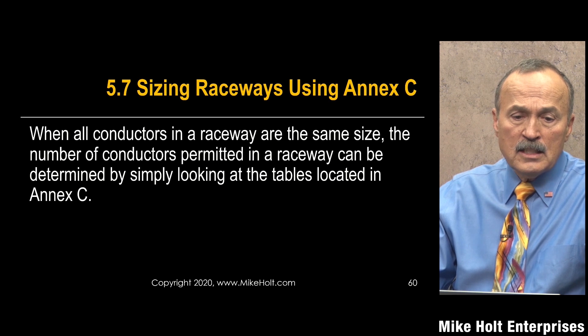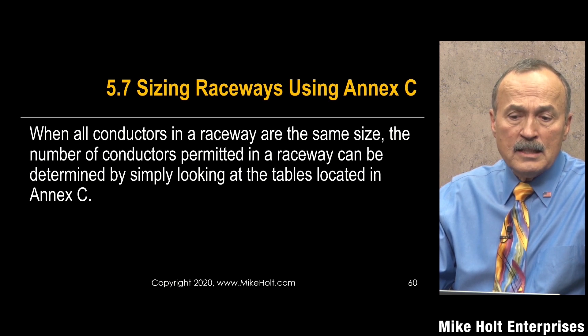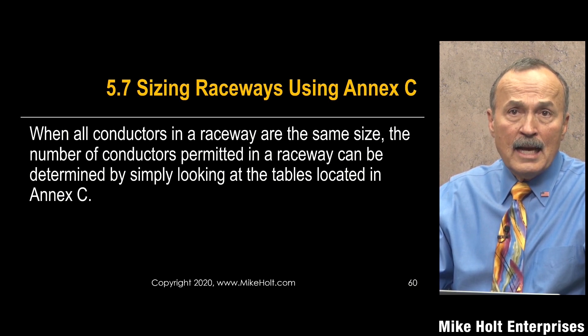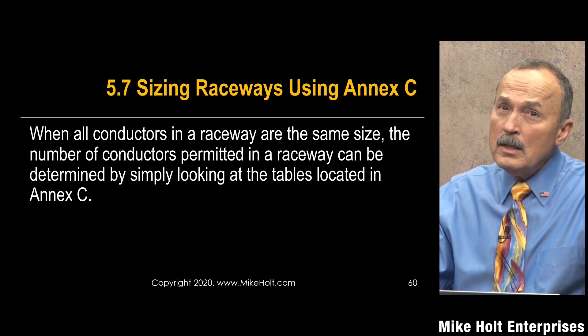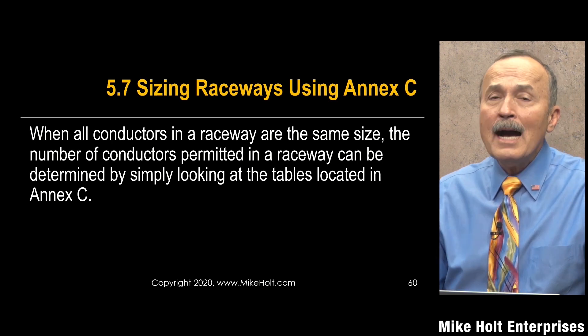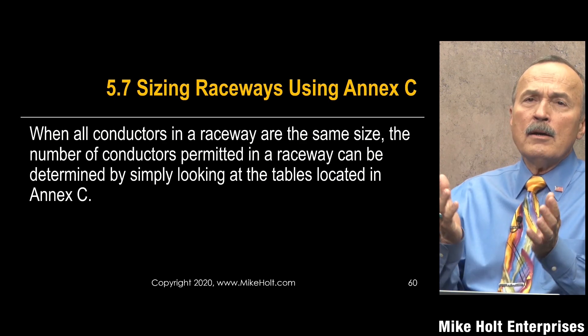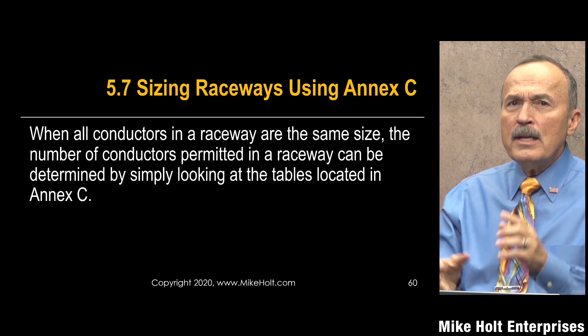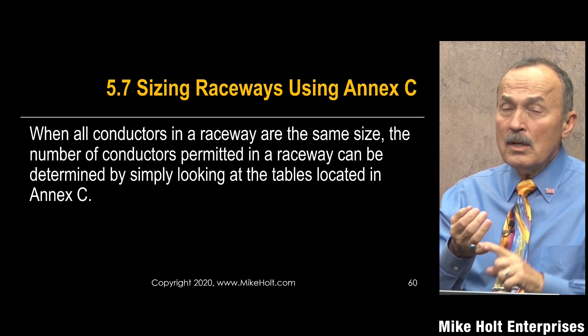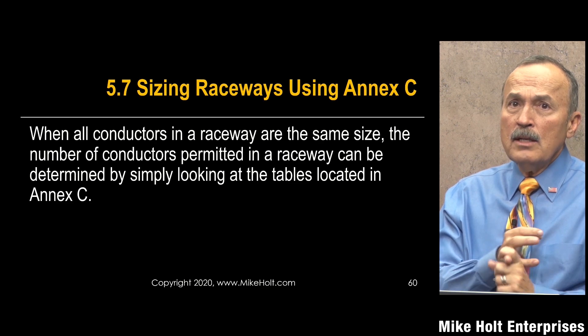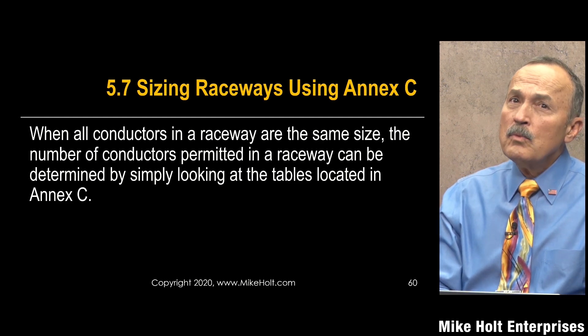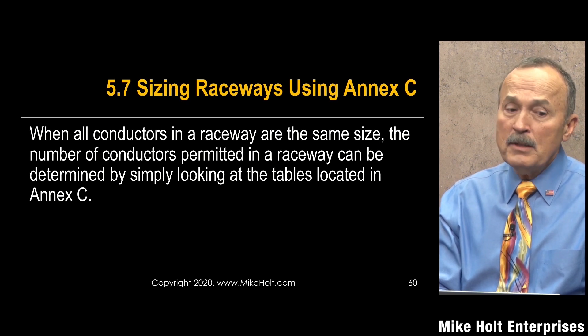Going to section 5.7 - where all conductors in a raceway are the same size, the number of conductors permitted shall be determined by looking up the tables in Annex C. An important point: some people go to Chapter 9 Table 5, take those conductors to Table 4, and verify the numbers. They think there are problems with Annex C, likely because of Note 7.